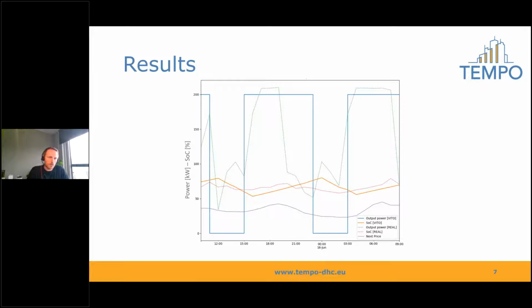You can see that our optimal plan was planning to run the CHP when the prices have a peak. But you also see in the results that the CHP did not completely follow our plan, because at 6 o'clock, for example, it stops running, while we said in our planning that it should have been running for a couple more hours. This can happen because, for example, the waste heat input was more than we expected or forecasted, so the CHP had to stop running.